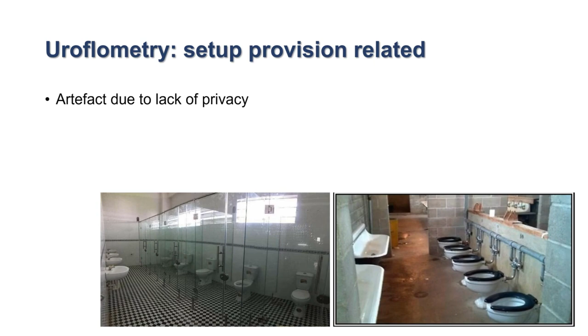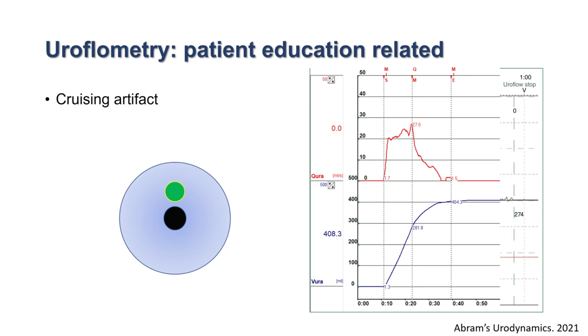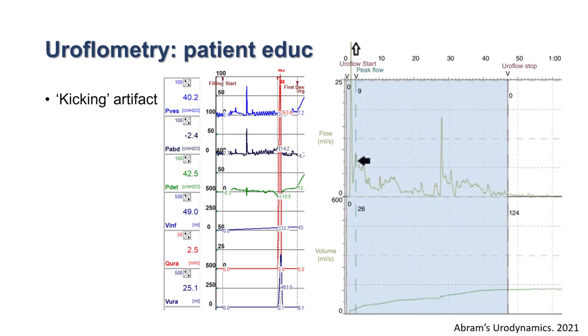In uroflowmetry, there can be problems of setup provision, like artifacts due to lack of privacy or an unaccustomed voiding position. There can be a cruising artifact, where the male patient is playing around on the funnel. The ideal is passing urine at one position in the funnel, which is not the hole. There can be kicking artifacts. All of us have seen that while recording the uroflow, the patient touches the transducer, and then there is a large sharp peak. Most of the software will have a provision for cutting it off during interpretation.